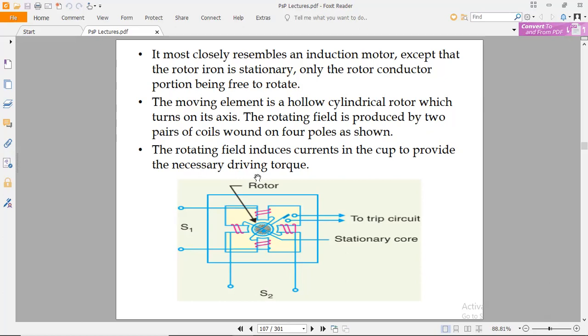So for the physical aspect of this relay, you can see there are two sets of coils which provide the supply to the poles, like S1 from this side and another pair of S1 further on this side. If you talk about the S2 section, this pole is wound from this side. The wire is wound further from this side in series in the coil S2, which is in series with each one. And further, the rotor is in a stationary condition at the starting instant, and this is the stationary core. So this part would be rotated and, to trip the circuit, provide a signal from this side.